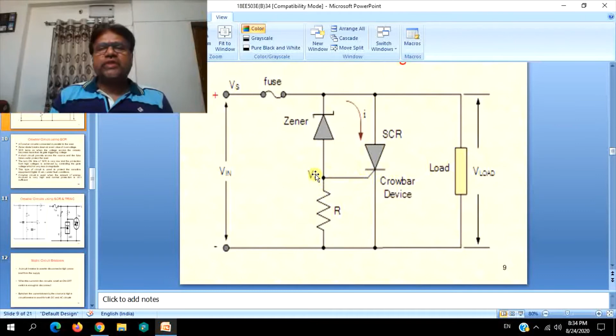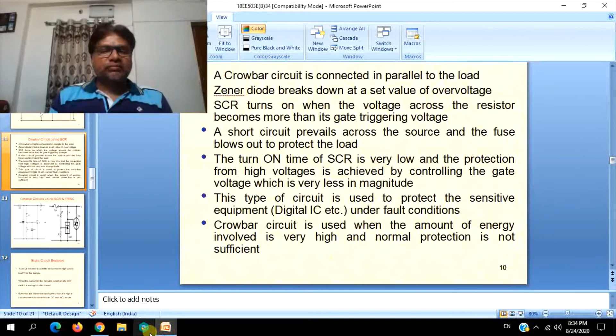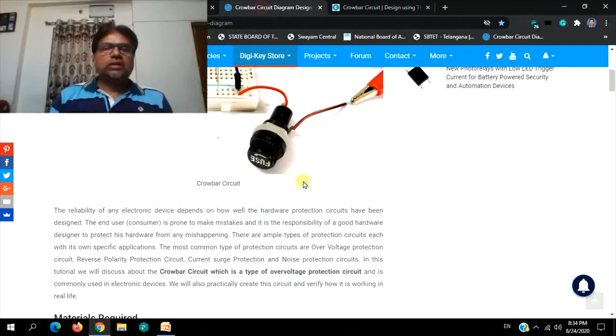This type of circuit is used to protect sensitive equipment under fault conditions. It is used when the amount of energy involved is very high and normal protection is not sufficient. When normal protection like overvoltage protection by SCR, the first circuit, is not sufficient, these crowbar circuits are utilized to isolate the circuits. We will just go through a simple crowbar circuit operation through a video shown.